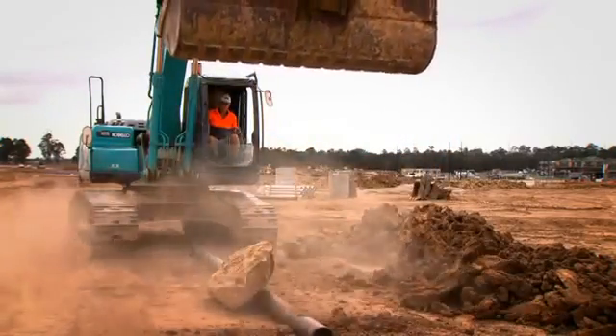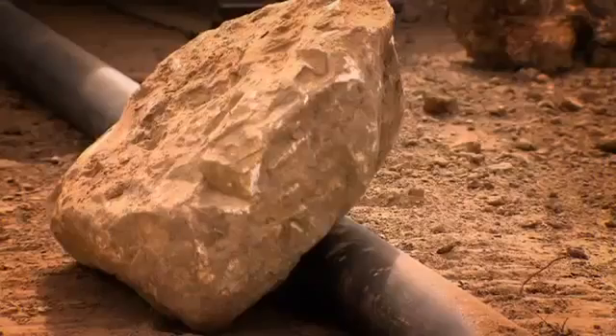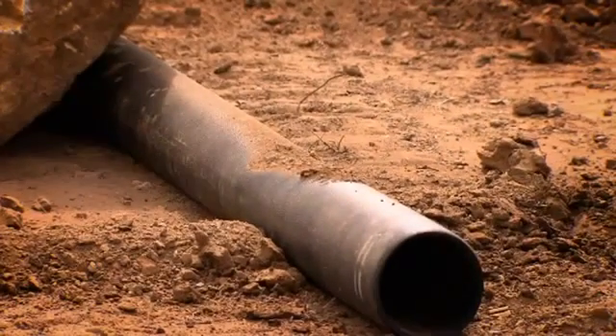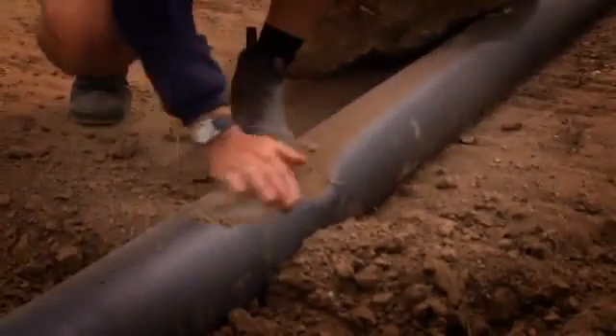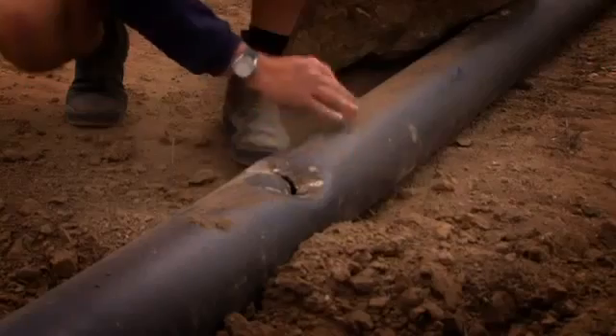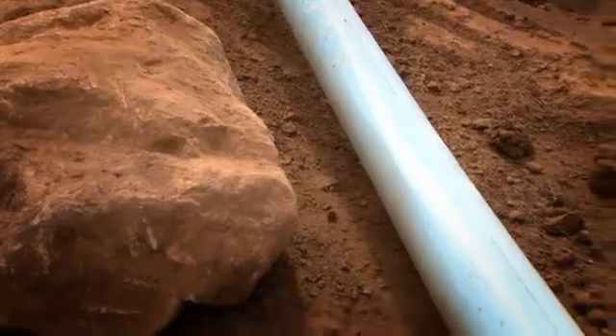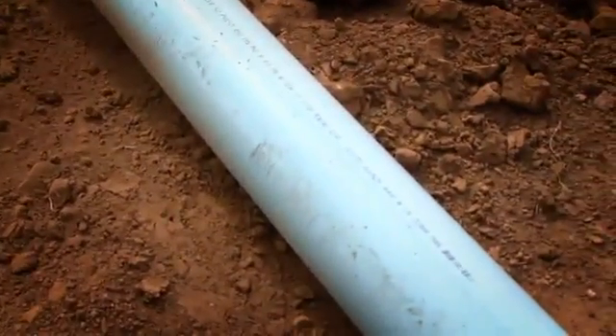Although the pipe's cement mortar lining was expected to crack internally and fall away, it was immediately apparent that the impact had seriously dented the surface of the ductile iron pipe. After brushing aside the dirt, a closer examination revealed a gash 100mm long by 10mm wide in the pipe. Although pipes would not be subjected to this type of abuse during installation, it clearly illustrates the toughness of PVCO compared to the ductile iron pipe.